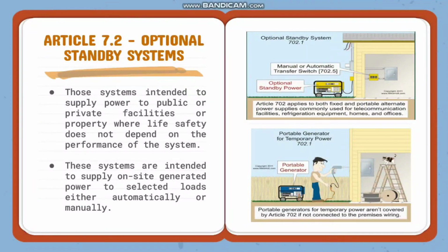So this article also applies to the installation of optional standby generators in homes, farm estates, small businesses, and many other applications where standby power isn't legally required. So, exception, a portable generator that provides temporary power like those used on construction sites doesn't fall within the scope of Article 7.2 unless the generator is permanently connected to the premises wiring.